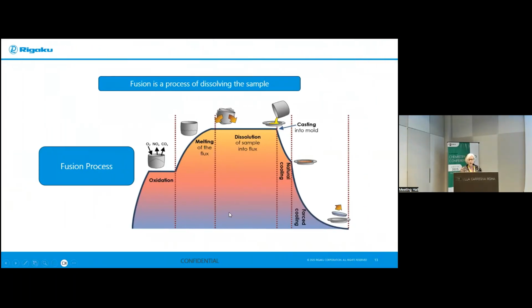So of course, fusion involves the process of melting a solid sample, which is a powder, into a molten glass, yes? So if you look at the process, it involves an oxidation step where we get rid of our volatile components like CO2, oxygens, and nitrous oxides, and all kinds of oxidation changes that happen within the material at a certain temperature for a certain period of time. The next step involves the melting of this oxidized sample or pre-treated sample into a flux. And then the dissolution of this by introducing steps like the mixing and the cooling and the casting, which then takes place, as you can see per the diagram here.